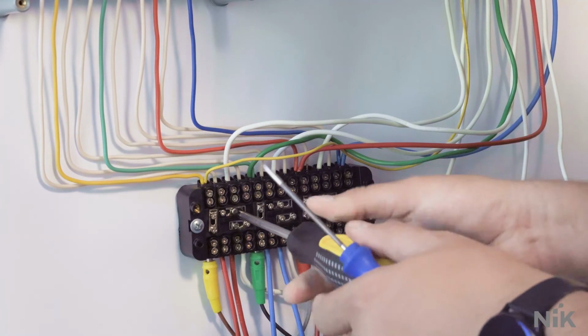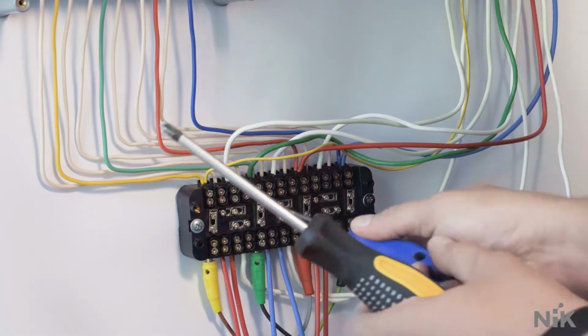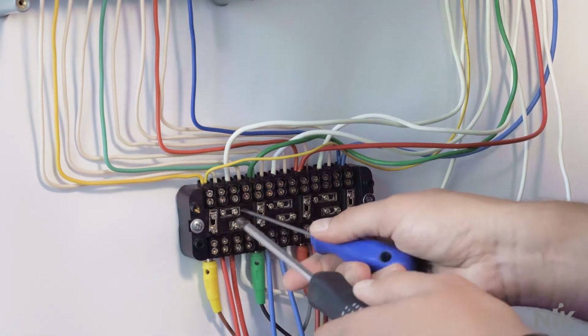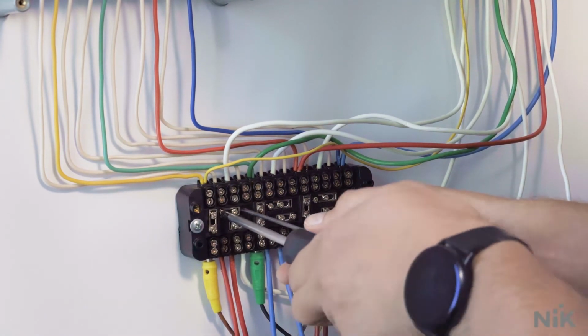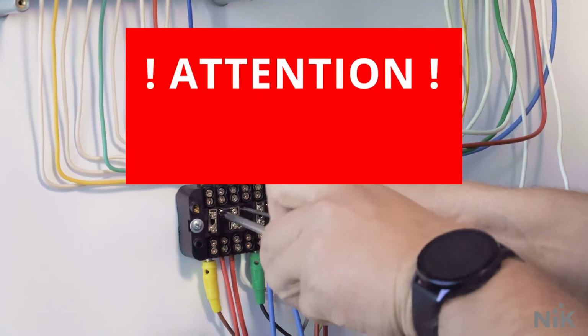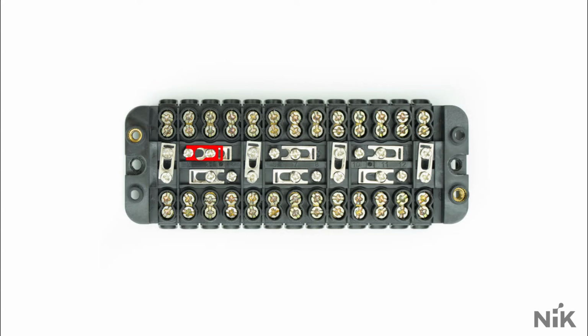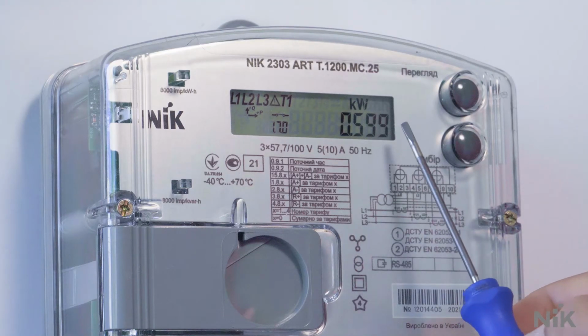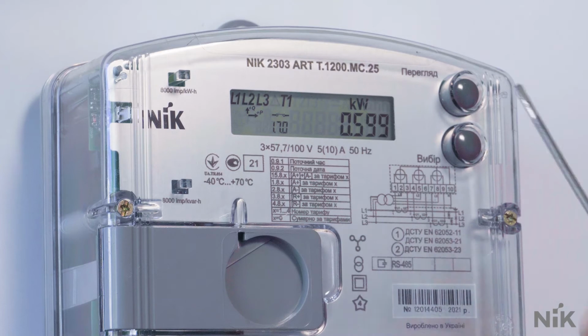Firstly, we unscrew the bolt which holds the jumper. Secondly, very accurately using isolated screwdriver, we push the jumper to the end. Attention, we are working under voltage. Thirdly, we tighten the bolt. After fulfilling of this operation, we can see the power which is used by this device has decreased at 1/3. That means that we shorted phase A. We proceed with the same for the two other phases B and C.